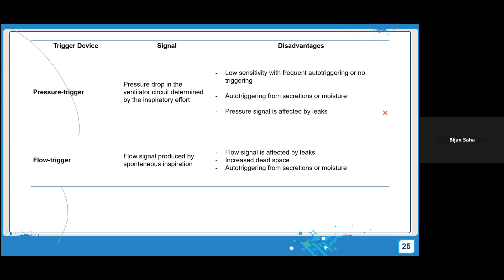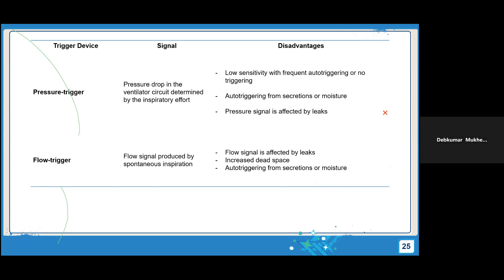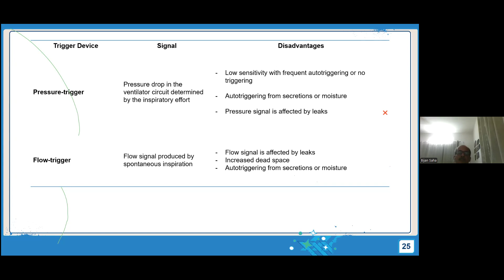The same thing happens in the flow trigger, and leak will also be a problem. In the flow trigger also, there is a constant flow of gas in the circuit that is known as bias flow. When there is a bias flow, there should be some change in the flow. But that change in the flow may be misdiagnosed as a breath because of the leak. As I have already told you, in the case of NIPPV there will be a lot of leak, and with that much leak in a small preterm infant, the pressure trigger and flow trigger may not be possible. That is why, in most ventilators, although they claim triggering, in real life this is not possible. It is practically difficult. Next slide, please.